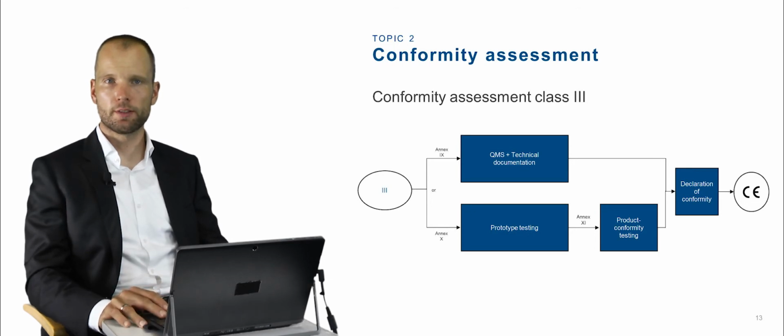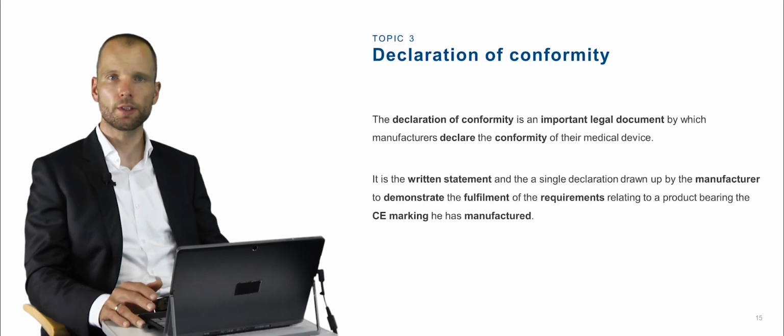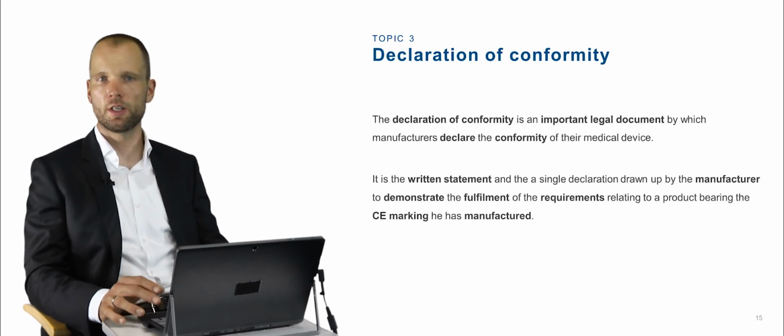product conformity testing. Let's talk about the Declaration of Conformity. The Declaration of Conformity is an important legal document by which manufacturers declare the conformity of their medical device. It is a written statement and a single declaration drawn up by the manufacturer to demonstrate the fulfillment of the requirements relating to a product bearing the CE marking he has manufactured.